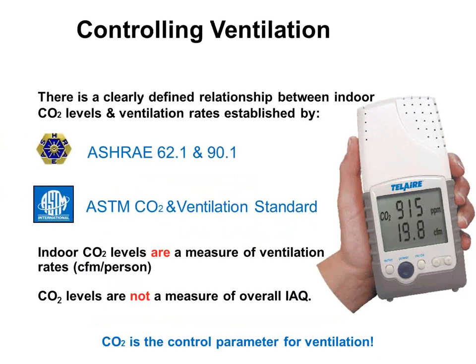So there are things involved here, like ASHRAE Standard 62.1, which is the ventilation standard for the country. The mechanical codes, such as the International Mechanical Code, piggyback off that standard and literally cut and paste the ventilation tables into their document, just like the energy code people, IECC, do with ASHRAE 90.1. ASHRAE is kind of the research backbone, if you will, and the code people take the ASHRAE stuff and write it in code stringent language.